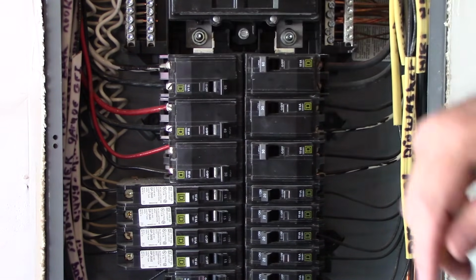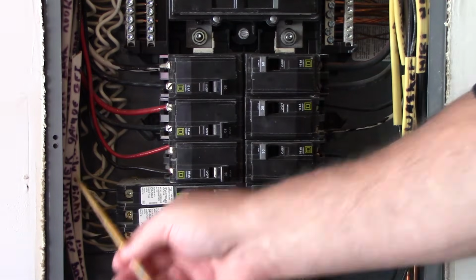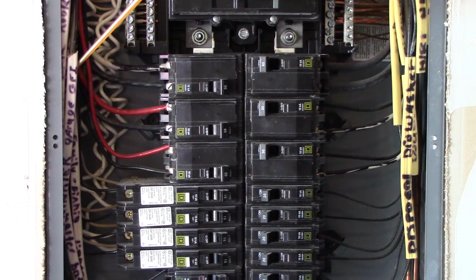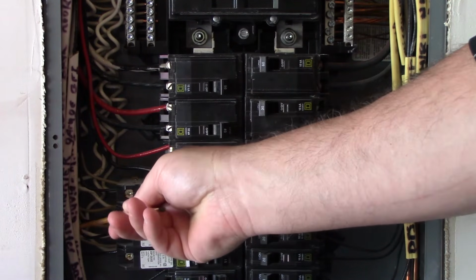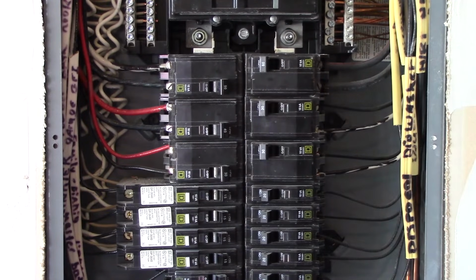Here we have a 40 amp, and it's got 8 gauge conductors to it, so we know that can easily handle 40 amperes, so we're good there. All of these breakers down here are 15 amps, and I can tell not just by the sheathing is white, but I also can tell by the size and ability of how freely they move that these are also a 14 gauge, so they're on a 15, so they're terminated okay.